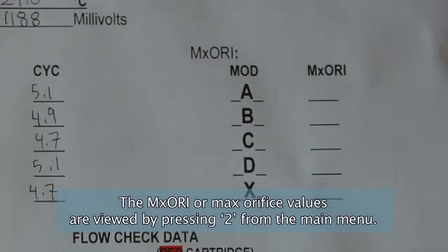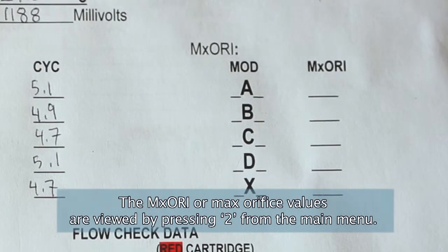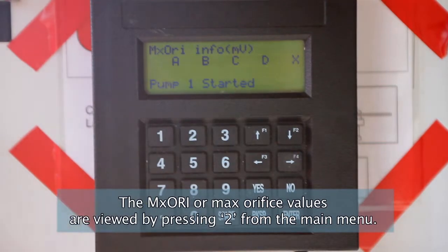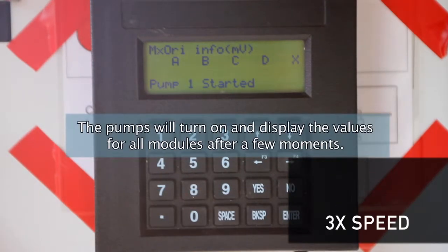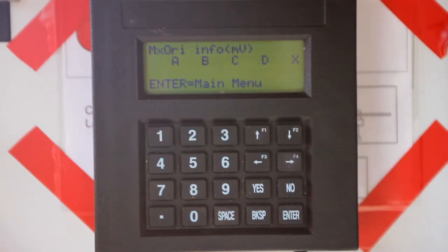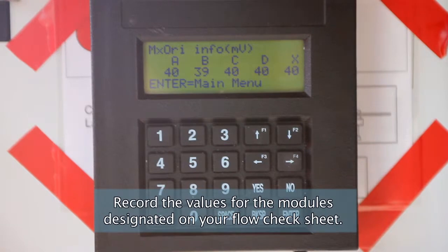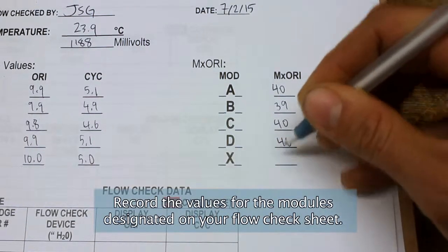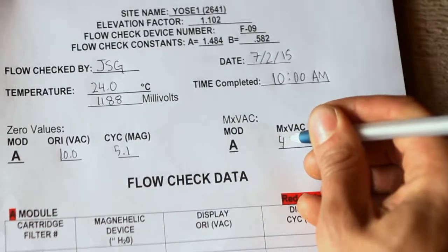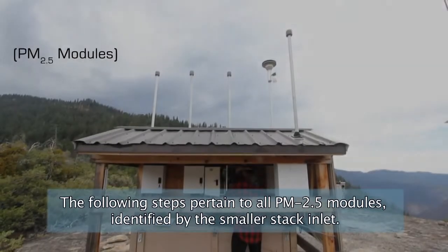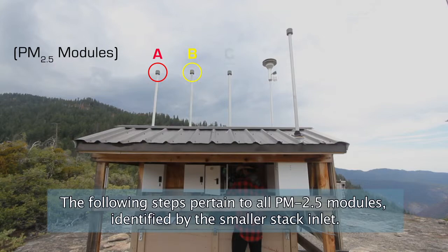The MX ORI or max orifice values are viewed by pressing 2 from the main menu. The pumps will turn on and display the values for all modules after a few moments. Record the values for the modules designated on your flow check sheet. The following steps pertain to all PM 2.5 modules identified by the smaller stack inlet.